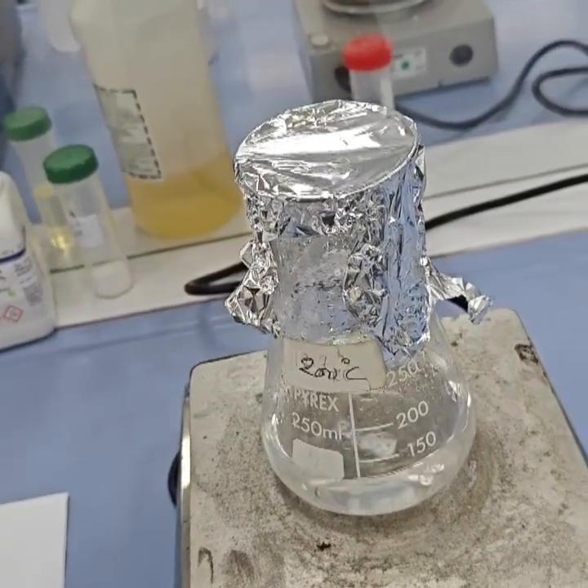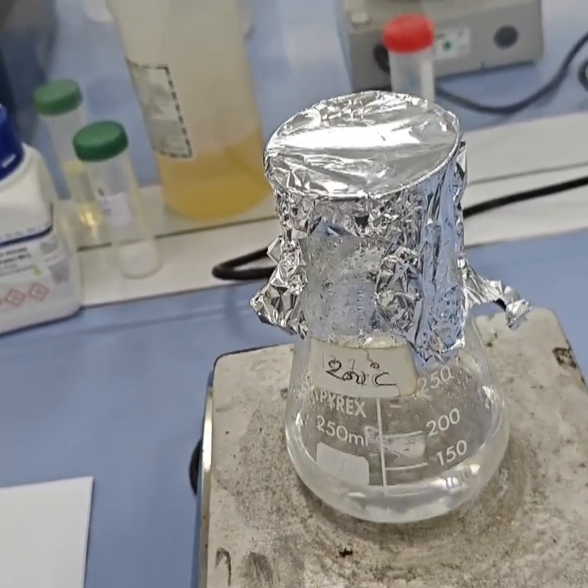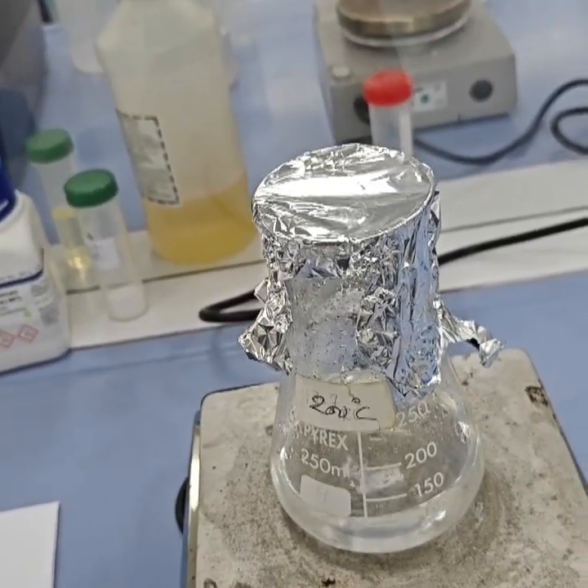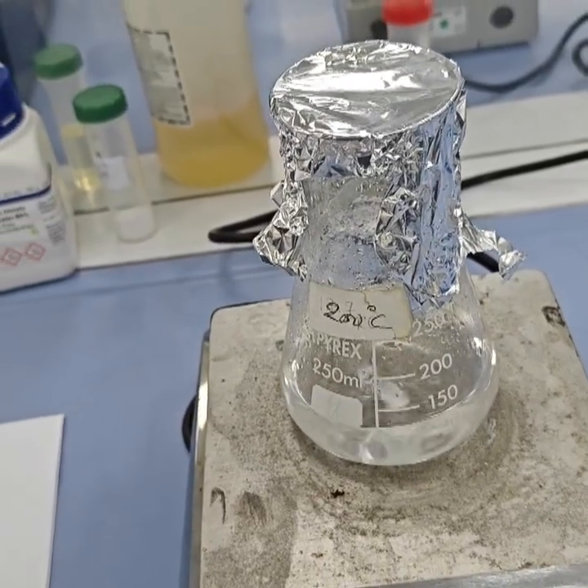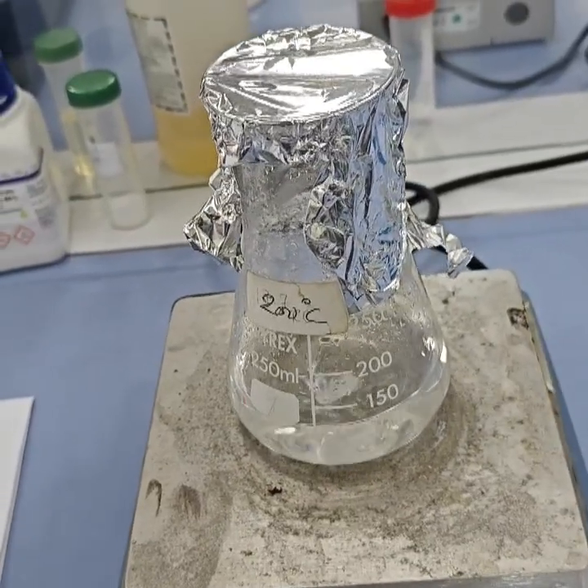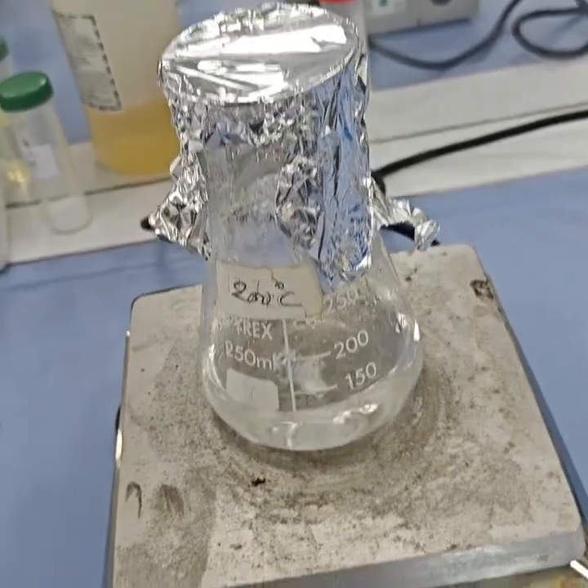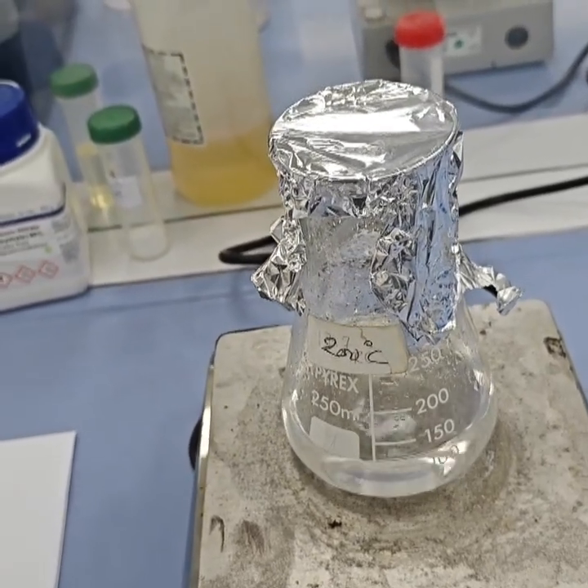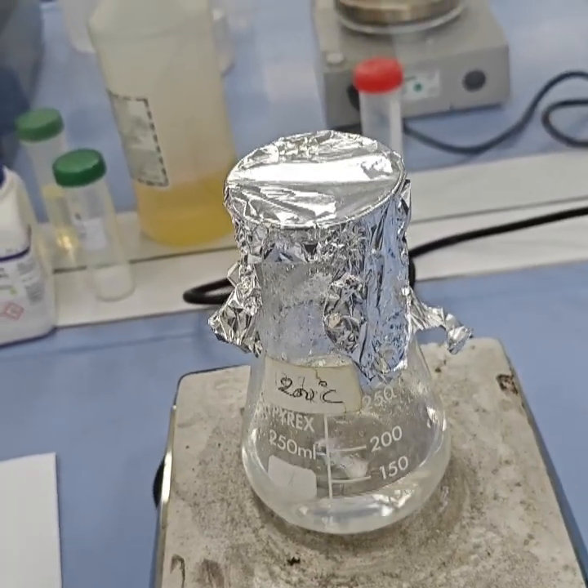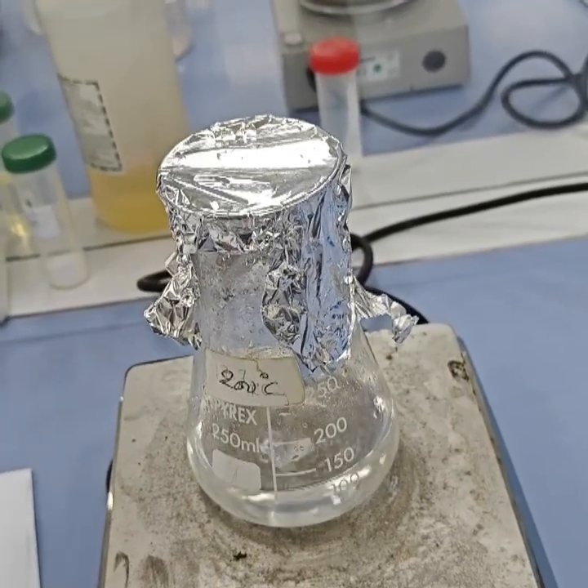Because it provides high ionic strength. Why not 3.5, 4, 4.5 and others? 3 molar provides high ionic strength for stable reference potential, matches the internal reference electrolyte concentration, prevents sample ions from entering the junction, ensures fast electrode response, and also prevents Ag plus leaching. Solutions that must never be used are distilled or deionized water, any salt other than potassium chloride, strong acid or base, which can corrode your probe, and organic solvents. You also cannot use calcium chloride, magnesium chloride, copper chloride, sodium chloride, or other ionic strengths such as 4 molar. So only 3 molar KCl is preferred.